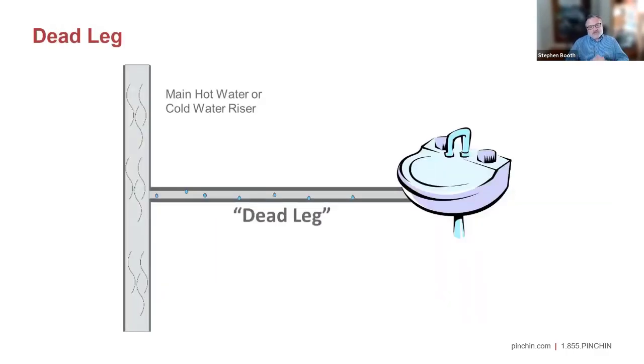One of the other places we see Legionella accumulate is in dead legs. We've traditionally thought of a dead leg as a situation where, say, there was a water fountain in your office that no one was drinking from, so you disconnected it but didn't remove the plumbing. That section from the riser to the water fountain that never has any flow is a dead leg. The water there is stagnant with little disinfectant, and bacteria like Legionella can grow within that space. In our very low occupancy buildings without a flushing system in place, many of our runs from the riser to the tap have effectively become dead legs over time.